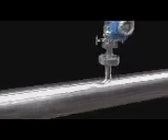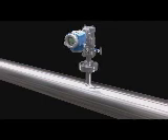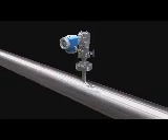One principle is flow measurement based on dynamic pressure detection using a pitot tube. Here is how this measurement method works. Pitot tubes have a rod-shaped measuring element that is inserted into the pipeline perpendicular to the flow direction. On the front and rear of this probe are several holes. Two separate tubes connect these holes to a differential pressure sensor. With its two pressure chambers, separated by a diaphragm, the tiniest pressure differences in the flowing fluid can be precisely measured.